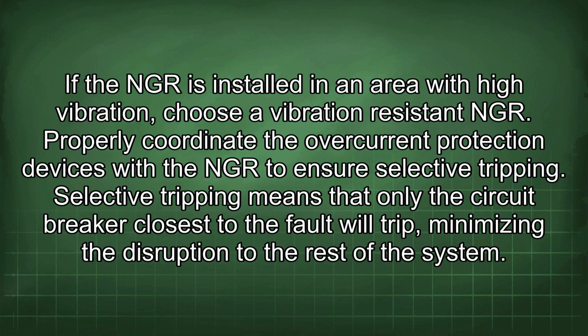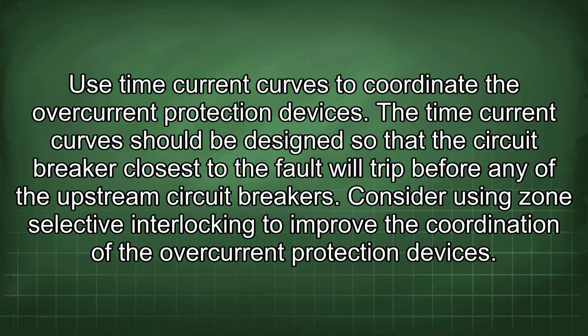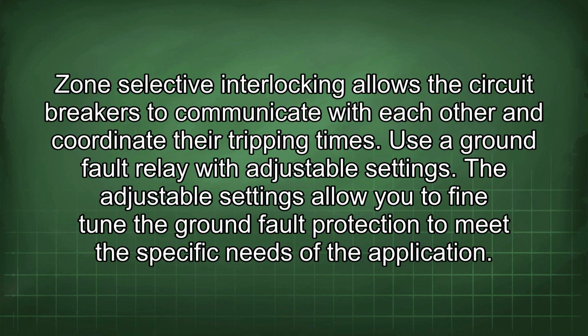Properly coordinate the overcurrent protection devices with the NGR to ensure selective tripping. Selective tripping means that only the circuit breaker closest to the fault will trip, minimizing the disruption to the rest of the system. Use time current curves to coordinate the overcurrent protection devices. The time current curve should be designed so that the circuit breaker closest to the fault will trip before any of the upstream circuit breakers. Consider using zone selective interlocking to improve the coordination of the overcurrent protection devices. Zone selective interlocking allows the circuit breakers to communicate with each other and coordinate their tripping times.